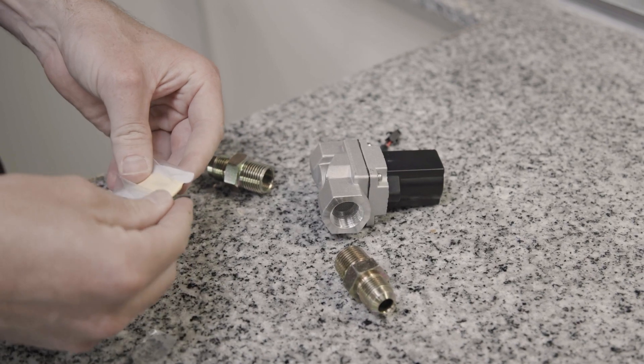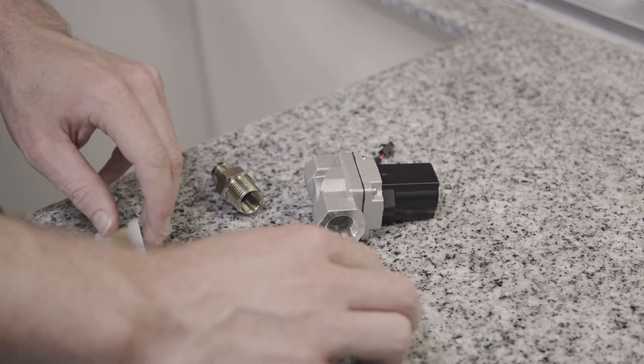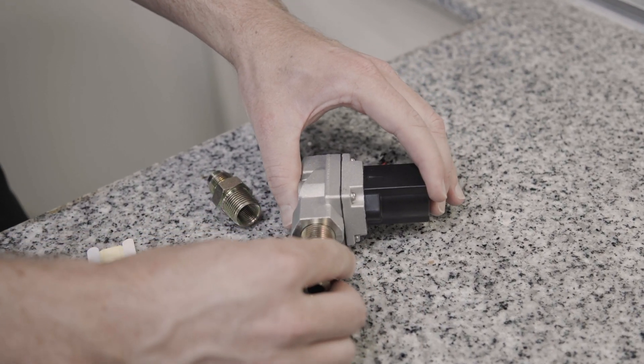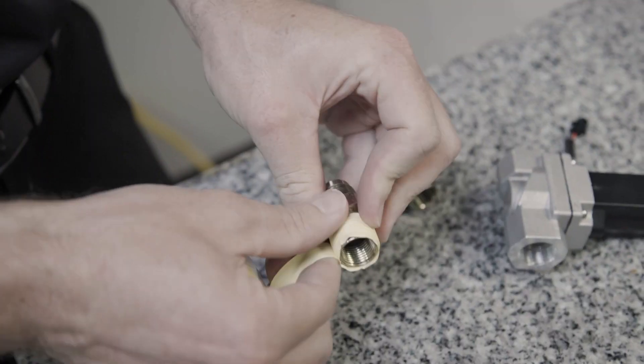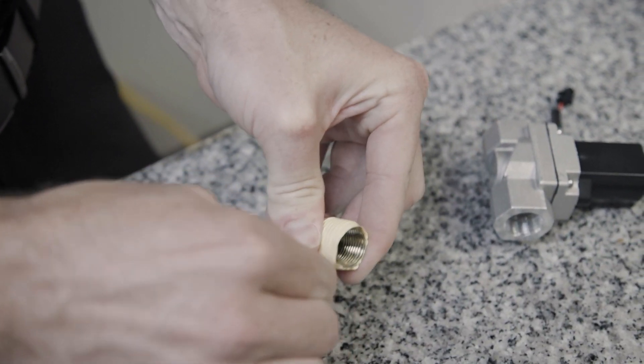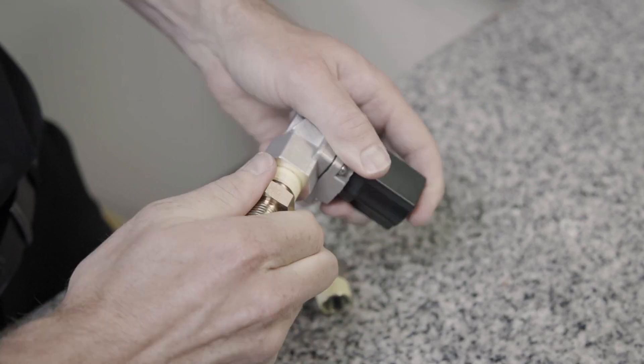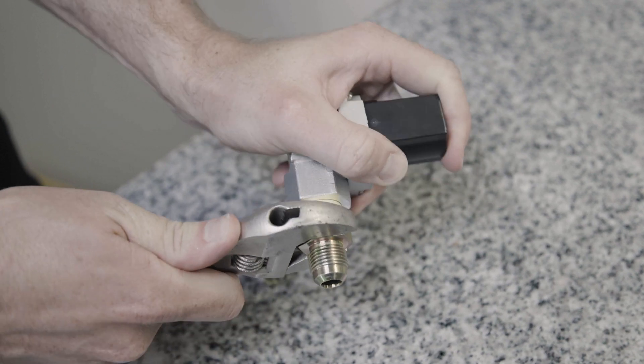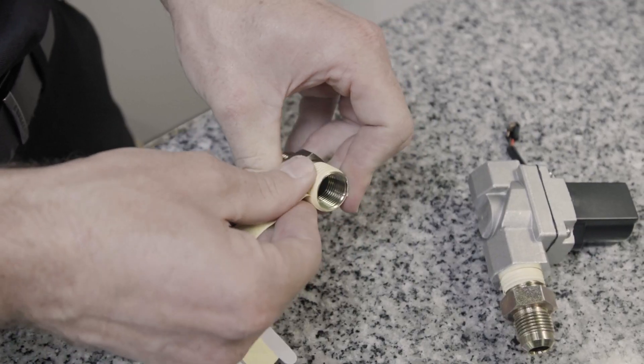Take the pipe sealant tape and apply that to both the ends of the adapters that are going to go into the solenoid. It's important to wrap this in the opposite direction in which you're going to thread it into the solenoid, just so that way the tape doesn't peel itself off.